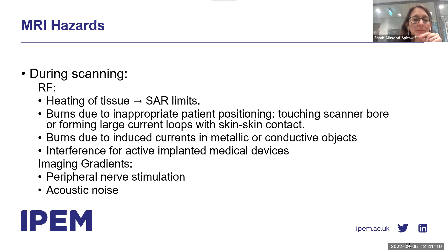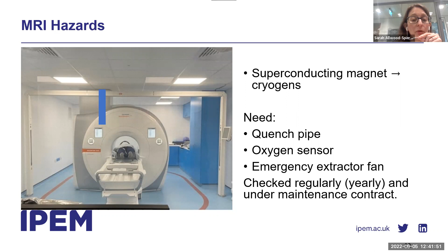Our scanner is cooled by liquid helium. There are now some scanners with closed systems and very small amounts of helium, just a few litres, but the majority of scanners have about 1,500 litres of liquid helium. In these, if there's a leak or a quench, a large amount of helium gas would be released. And if this is released into the scan room, this displaces the oxygen and presents a risk of asphyxiation. So we need a quench pipe to ensure that any helium gas vents to the outside, an oxygen sensor in the room, which will alarm if the oxygen levels drop, and an emergency extractor fan to clear helium gas from the room.